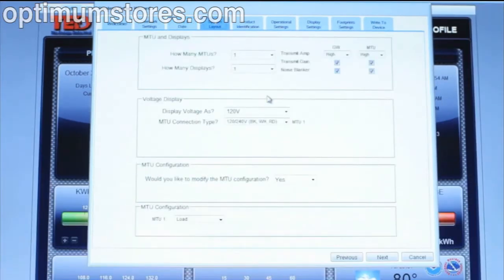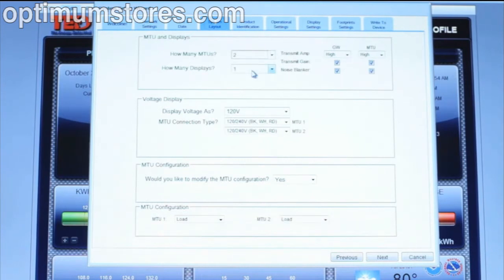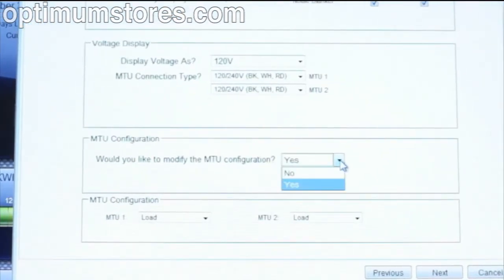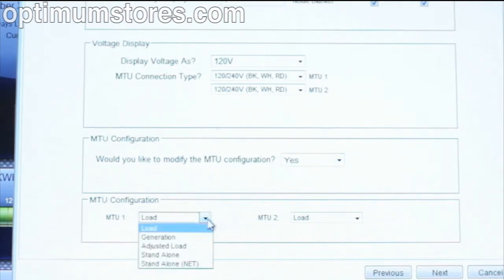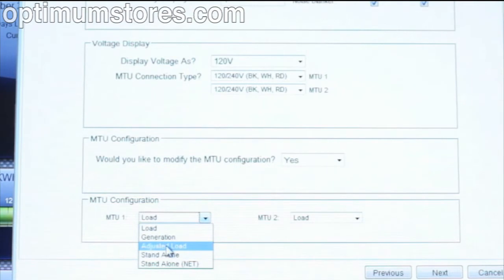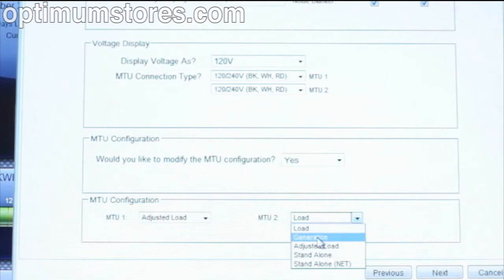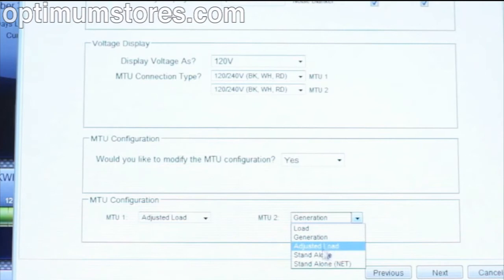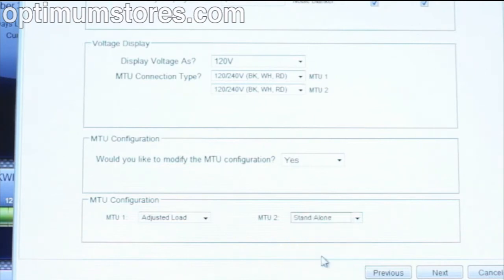The System Layout tab is extremely important if you have multiple panels or you have solar or wind generation. If you do have solar or wind generation, or you are monitoring a single circuit, you want to answer yes to change the MTU configuration. Solar and wind generation customers should set MTU1 to adjusted load and connect this MTU to the main lines feeding the panel. Set the MTU monitoring your wind or PV system to generation. Customers wanting to monitor a single circuit would select Standalone for that particular MTU so that the totals from this MTU will not be added to your overall calculations.